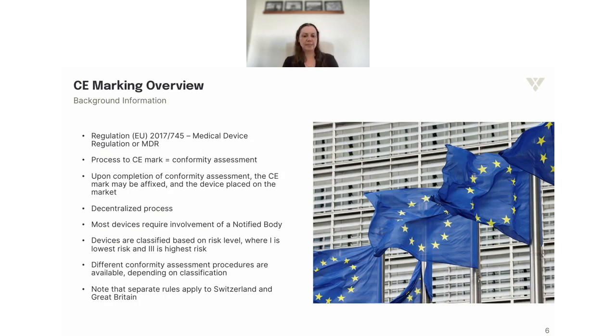The process to CE mark is called conformity assessment. And once you've completed that conformity assessment process, you can affix the CE mark to your device and then place it on the market. Now, unlike the US or in other geographies, CE marking is a decentralized process. This means that you don't have a central regulator such as the FDA or PMDA in Japan or TGA in Australia, for example, that look at your device.